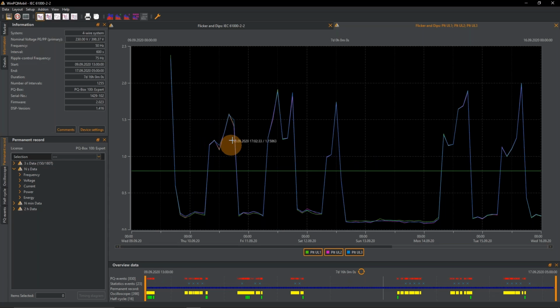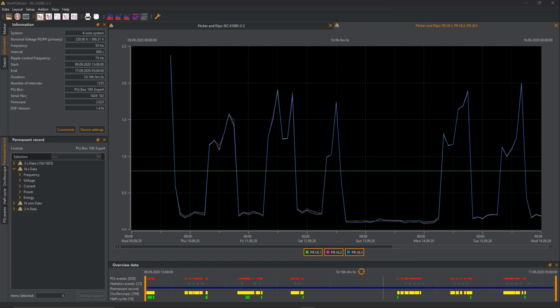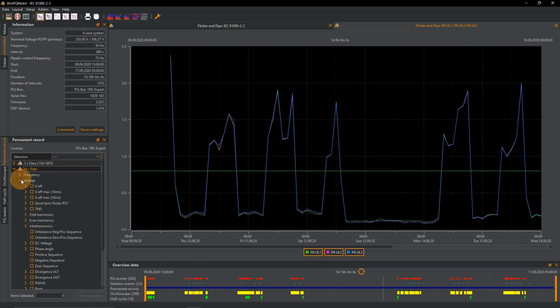And I see the long-term flicker violated the limit value a lot. So now it's time to find out the cause. Let's investigate the permanent record data. So first of all, I go to my permanent record over here, and I will select the voltage. I will select the RMS value of my voltage and the RMS value of my current to just get a first impression of what the possible cause could be.